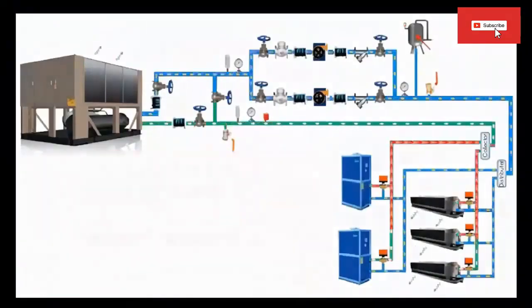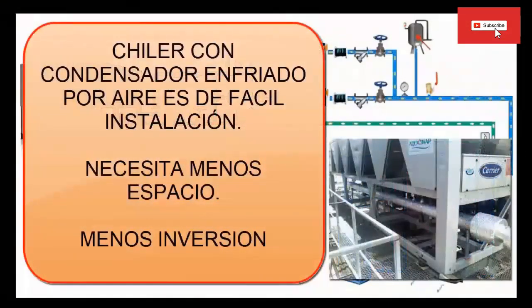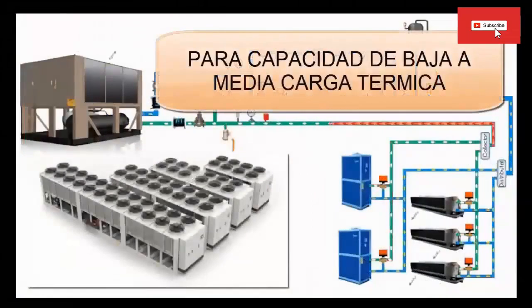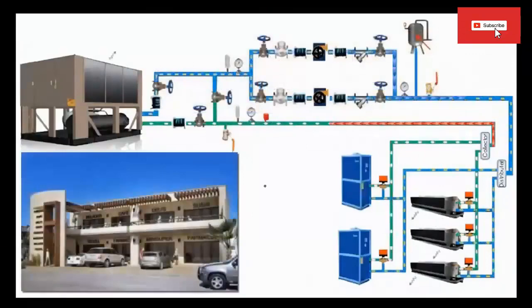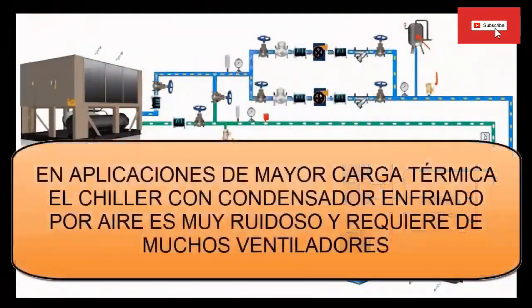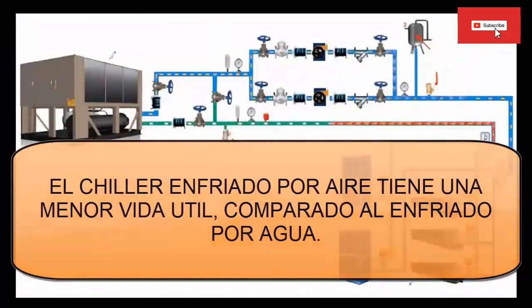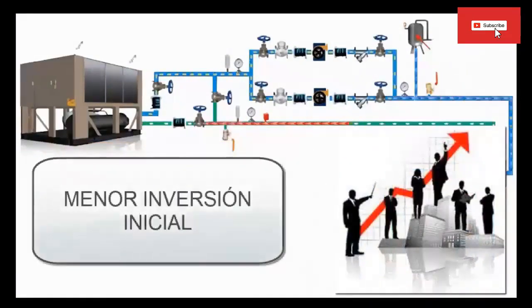The air-cooled condenser chiller requires less maintenance and less complexity to install and monitor. The air-cooled chiller is widely used for machine cooling in small factories. It is also used to condition the environment in smaller shopping centers. To dissipate the thermal loads, the air-cooled chiller requires a lot of space and is noisy equipment, which must be considered in urban environments with limitations or strict regulations. The air-cooled chiller generally has a shorter useful life, as it handles higher pressures than water-cooled chillers. The investment in installations with air-cooled chillers is lower than in systems with water condensation.